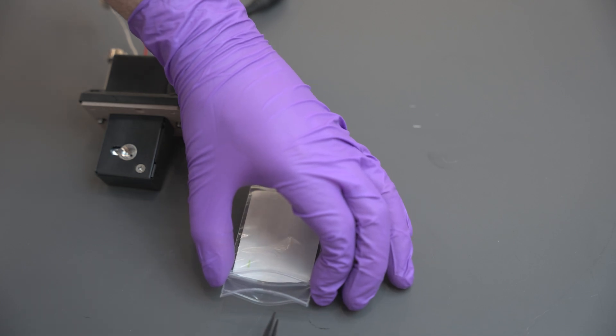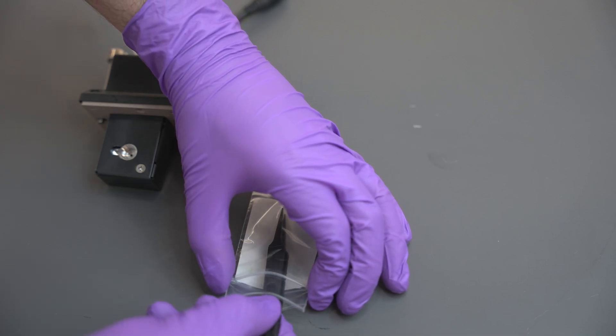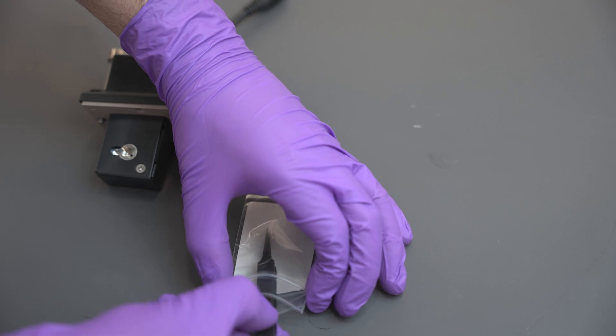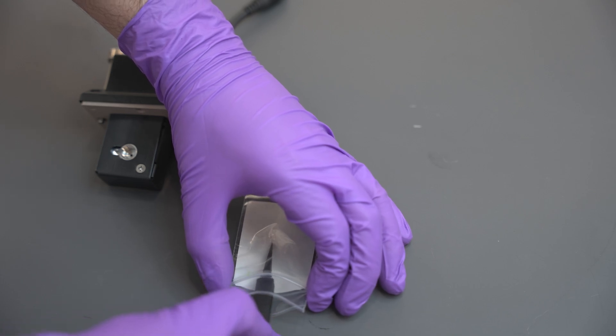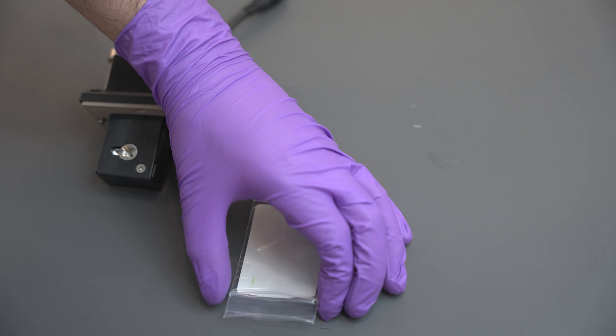Remove the lenses from their packaging with the plastic tweezers and set them on a clean piece of wiping paper. Carefully remove one gasket from the packaging with the plastic tweezers and place it directly into the flow cell housing.